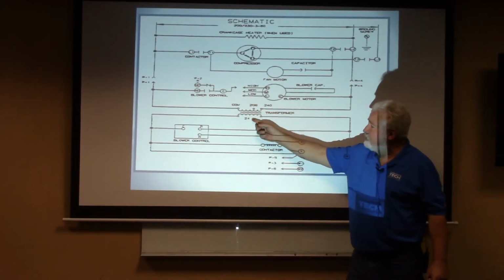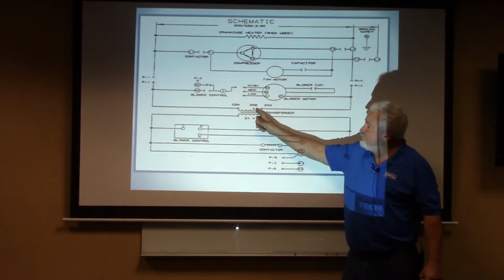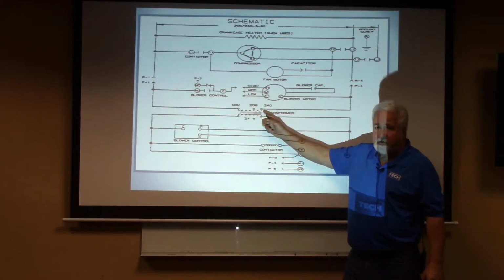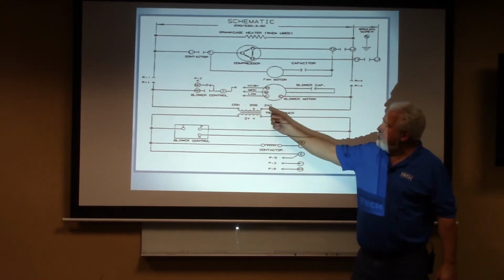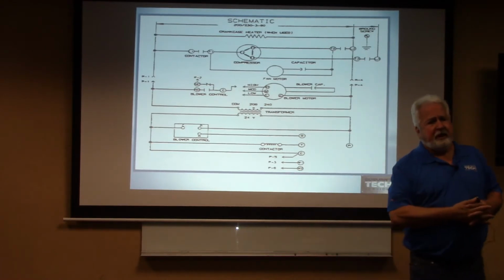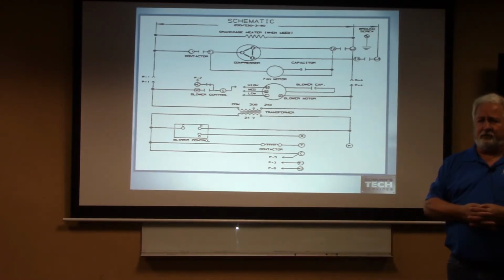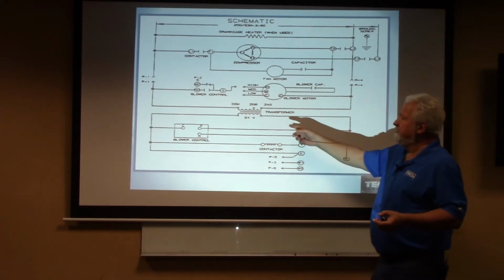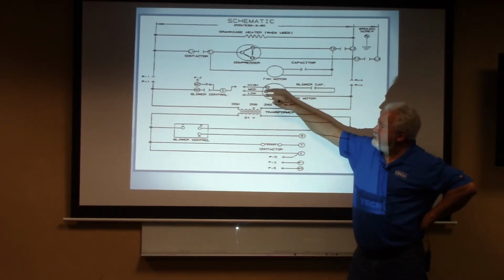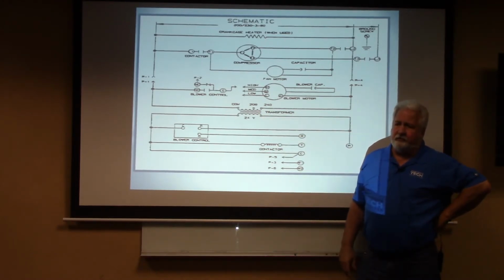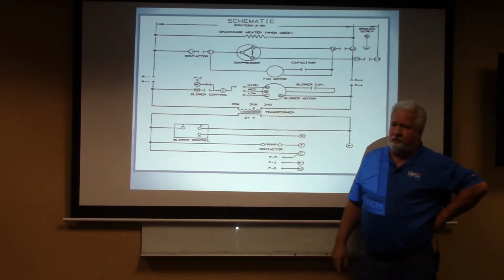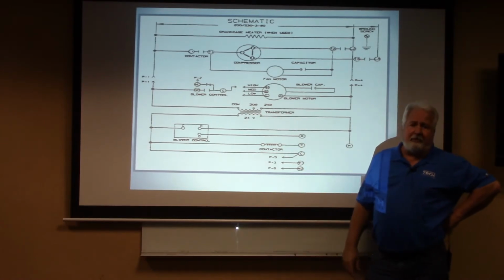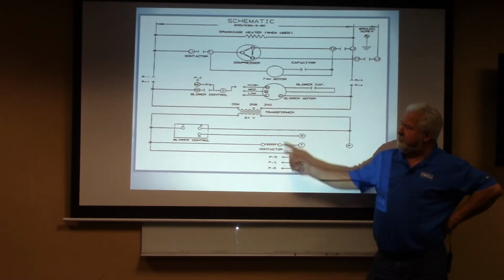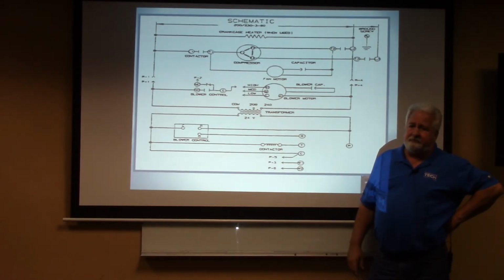Now notice this right here on the transformer. Here's that piece again. You've got your 24 volts, your common, and your 208 is tapped off a little bit sooner than that 240 volt. So what if I had my 240 volt transformer and I applied 208 volts to it? What would my output voltage be? If this is a 10-to-1 ratio, because it's 240 to 24, and I applied 208 volts to that 240, what's going to be my output? About 20.8 volts, is that right?